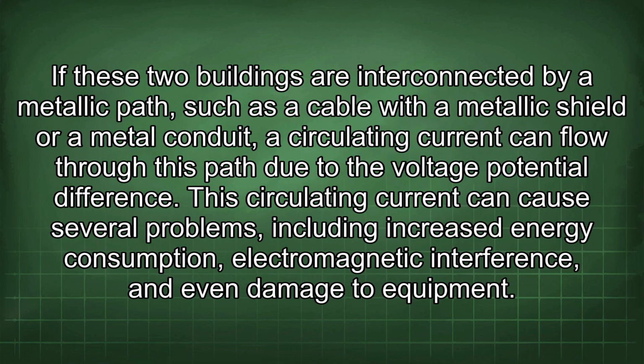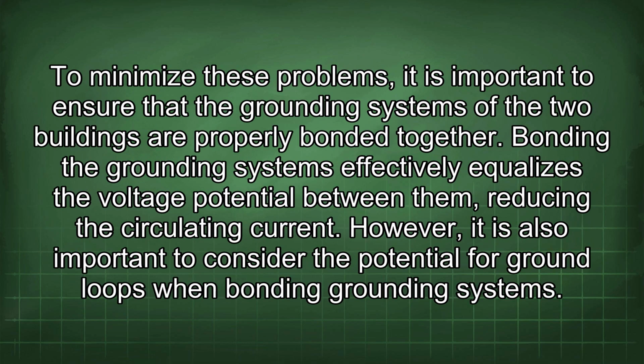If these two buildings are interconnected by a metallic path, such as a cable with a metallic shield or a metal conduit, circulating current can flow through this path due to the voltage potential difference. This circulating current can cause several problems, including increased energy consumption, electromagnetic interference, and even damage to equipment. To minimize these problems, it is important to ensure that the grounding systems of the two buildings are properly bonded together. Bonding the grounding systems effectively equalizes the voltage potential between them, reducing the circulating current.